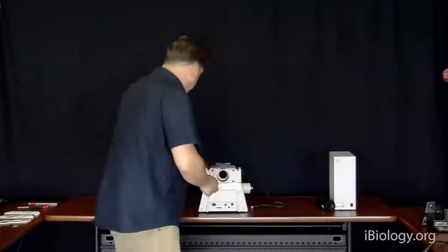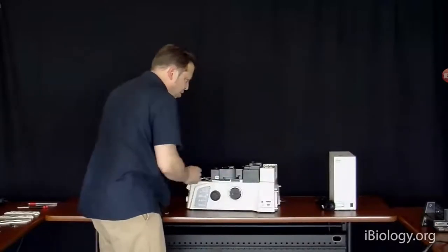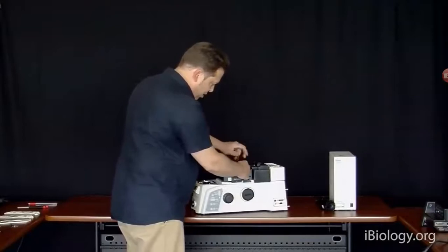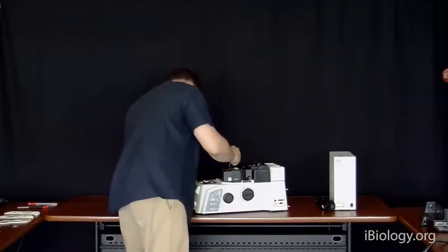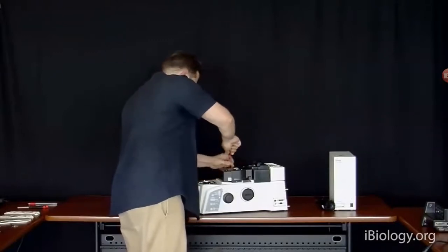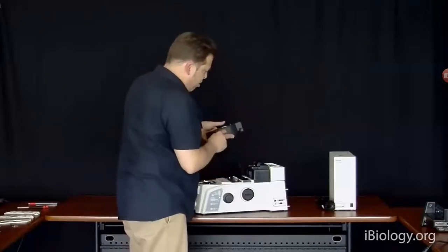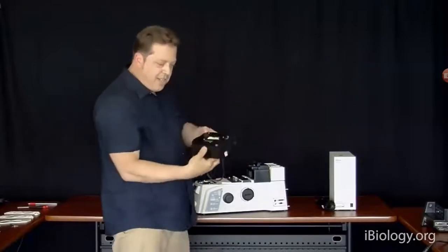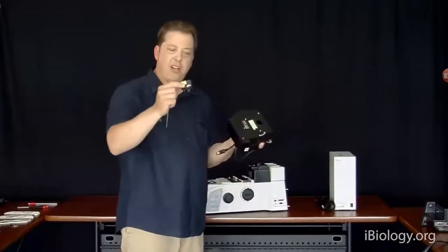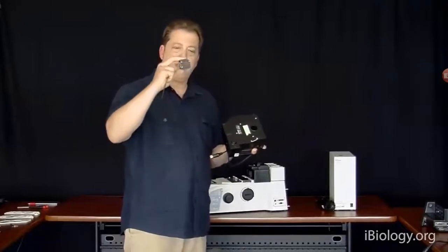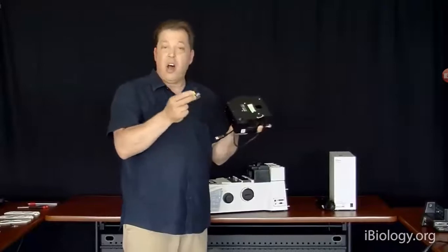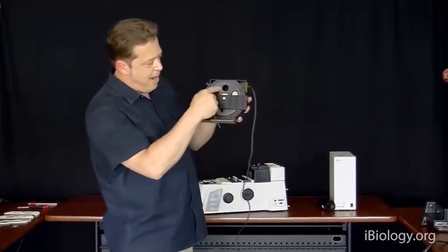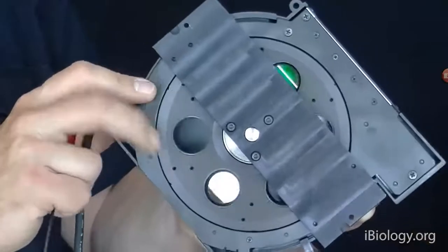Okay. So now we're basically down to a block of alloy with one last component, or two last components if we consider the imaging for it. So let's just take this off here. And this component is called the epifluorescence turret. The epifluorescence turret on the microscope basically just holds those fluorescence filter cubes that we've talked about, which will have a dichromatic mirror, excitation filters, and barrier filters, depending on the type of fluorescence filter we're using. The turret, if you see from the bottom, basically is a ball bearing turret with a motor in the middle and can switch the different fluorescence channels here.